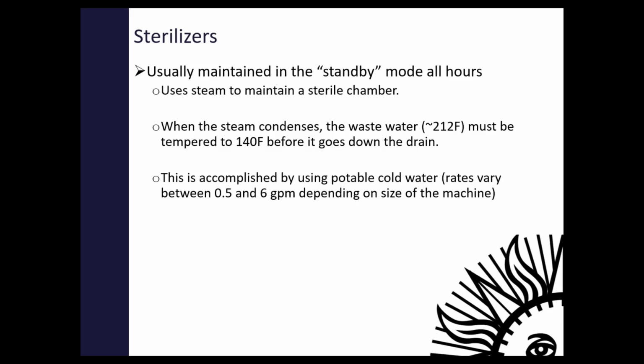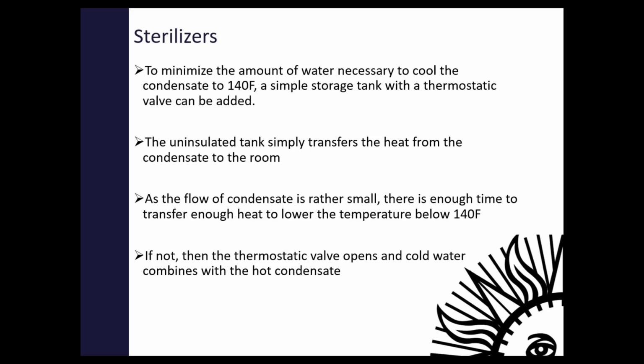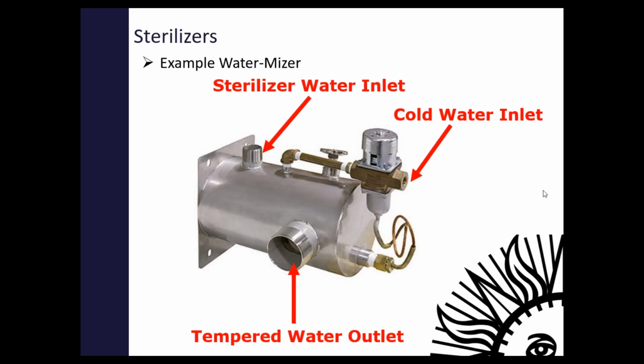Another thing is usually they'll temper the water coming out of the sterilizer, because you have to temper it down to 140 degrees generally before putting it through the storm drain. So they put a continuous supply hooked into the discharge from your sterilizer to make sure that it's always below 140. But when your sterilizer isn't running, that continuous supply is still pumping, up to 6 GPM just down the storm drain. So you just need to make sure there's either a solenoid valve there, or more ideally, you install this water miser tank that effectively just stores the discharge water in a tank, and it radiates the heat to the room. And then if the water level rises too high and it needs to discharge to the storm drain, it'll temper it back down with the domestic cold water through this sensor right here. Once that goes above 140, this valve opens and this chamber will be tempered down to 140, and then there's supposed to be a solenoid valve here as well. And then this valve would open and discharge.